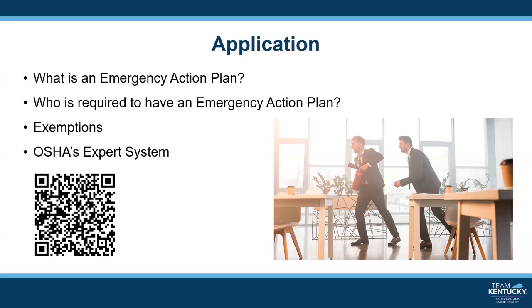Per OSHA's 1910.160(b)(10), if a workplace is protected by a total flooding system, which provides agent concentrations exceeding the maximum safe levels set forth in paragraphs (b)(5) and (b)(6) of 1910.162, then the facility is required to have an emergency action plan.